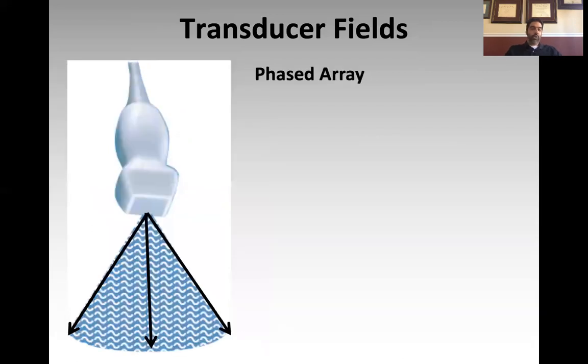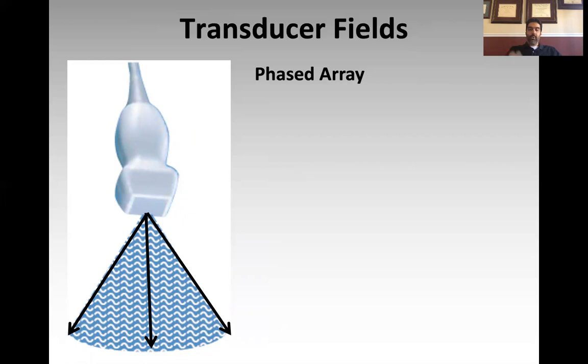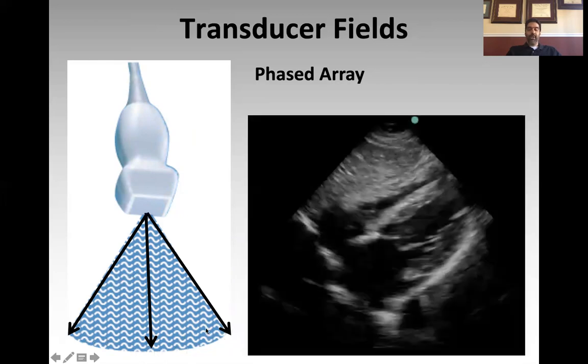The workhorse probe of critical care, and I think the most unique probe in your armamentarium, is the phased array probe. The phased array probe is special because instead of having crystals grouped in a linear fashion along the nose, the crystals are grouped tightly together at the center of the probe. Not only do the crystals vibrate and shoot out sound, but the entire array oscillates back and forth. So the crystals vibrate and the array itself oscillates back and forth, creating a field that is very narrow at its origin.